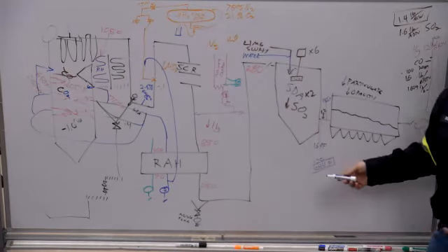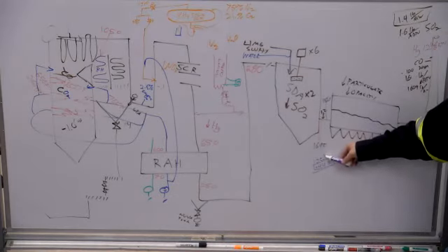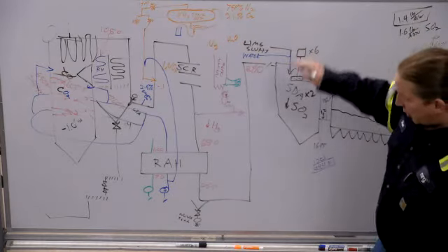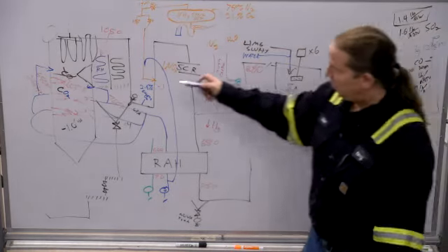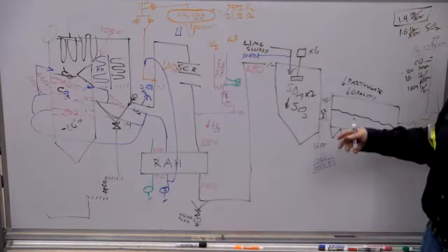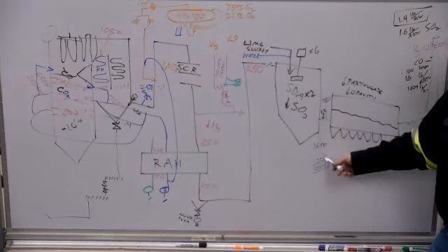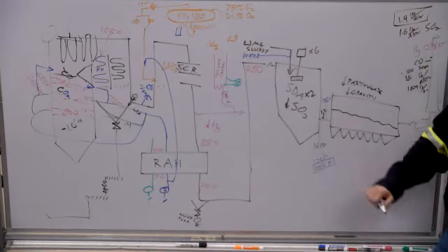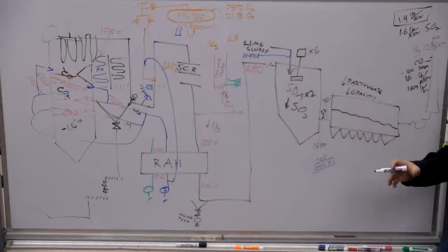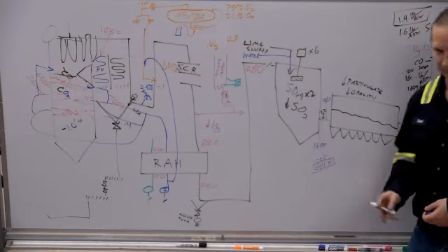So that's complicated. Why do we make it more complicated? We made it more complicated because that 125 changes sometimes, and it changes with load, and it changes when a soot blower runs, and it changes when the water cannons run, and all these things put extra moisture in the air. It sees this 125 will see that, and it will adjust so that you can constantly run a little bit colder than you would have if you were in temperature control and get away with it.